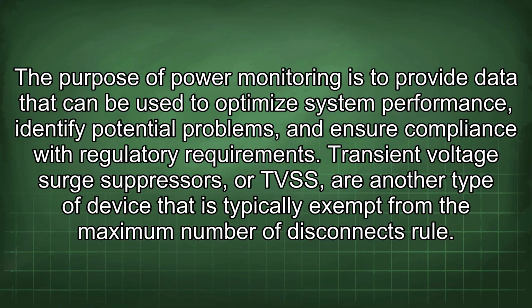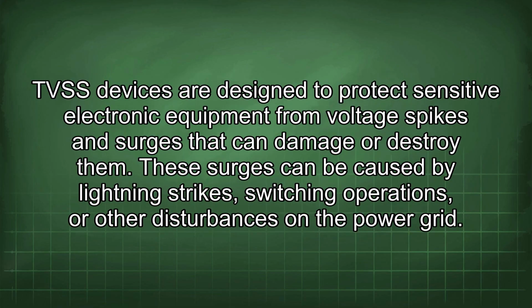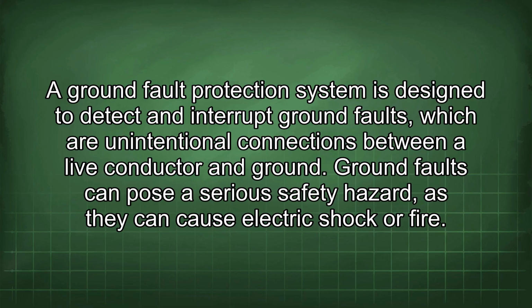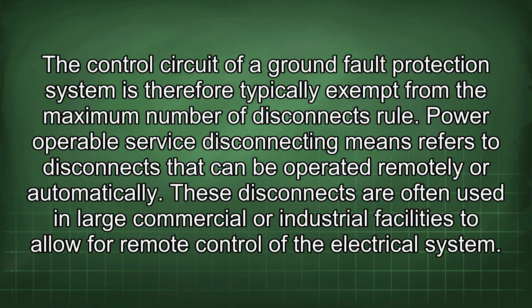Transient voltage surge suppressors, or TVSS, are another type of device that is typically exempt from the maximum number of disconnects rule. TVSS devices are designed to protect sensitive electronic equipment from voltage spikes and surges that can damage or destroy them. These surges can be caused by lightning strikes, switching operations, or other disturbances in the power grid. A ground fault protection system is designed to detect and interrupt ground faults, which are unintentional connections between a live conductor and ground. Ground faults can pose a serious safety hazard, as they can cause electric shock or fire. The control circuit of a ground fault protection system is therefore typically exempt from the maximum number of disconnects rule.